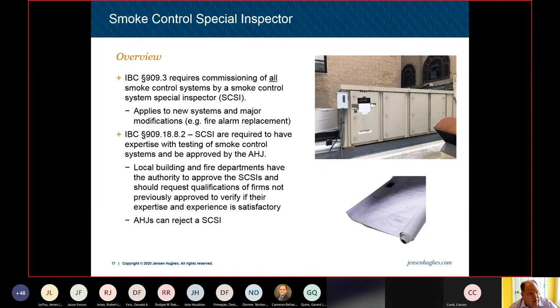I saw that we did have some AHJs among the participants in the video chat today. Local building and fire departments have the authority to approve the smoke control special inspectors, and they should request qualifications of those firms not previously approved to verify their expertise. And actually, AHJs can reject smoke control special inspectors. So they have not only the power to approve, but they could actually reject them. But that smoke control special inspector is really supposed to assist with the big picture view and the holistic integration of those systems into one cohesive smoke control system that performs like it should per design.